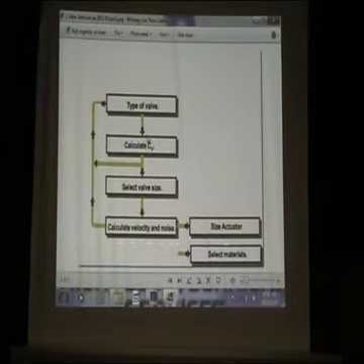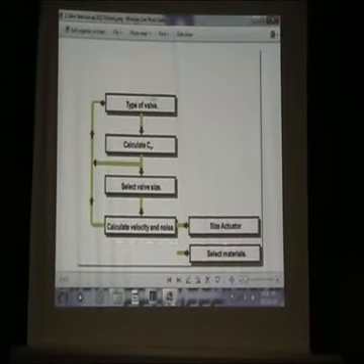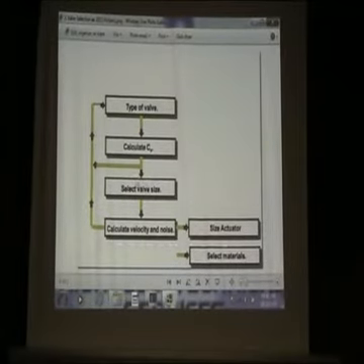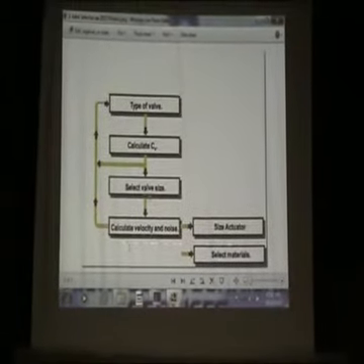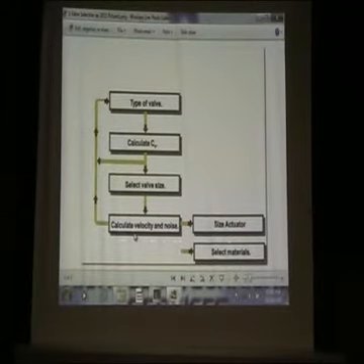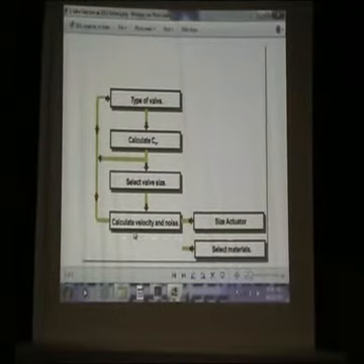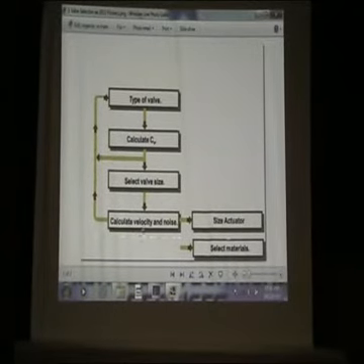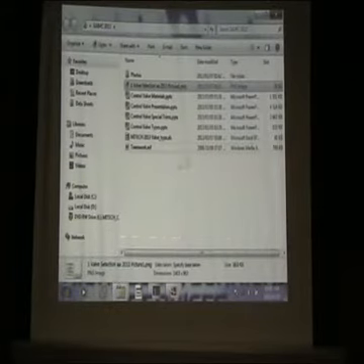Then you calculate the flow, and when you've calculated the flow, you would know what type of valve you need to use. Then you select the valve with the size, and then you calculate the noise, because we said you cannot put a 100 decibel valve into Sasol, because the standard says 85 decibel maximum. So you need to put something into your valve to accommodate that. We said that earlier. And then you size the actuator and the materials. That's just, but later in the control valves you'll see that.